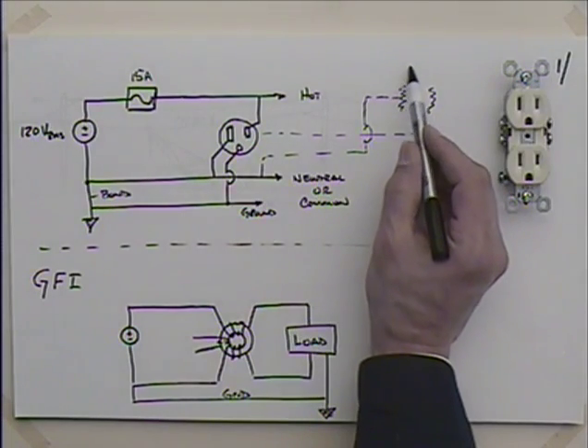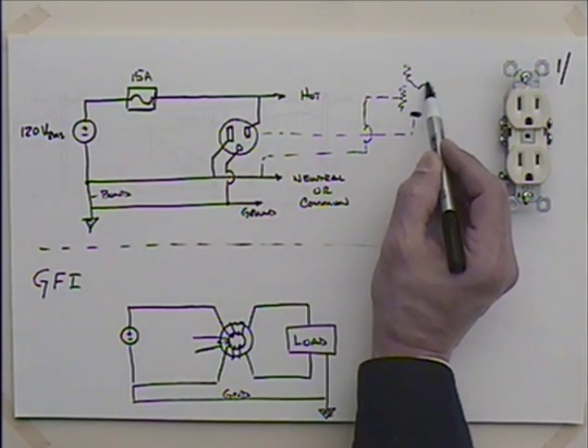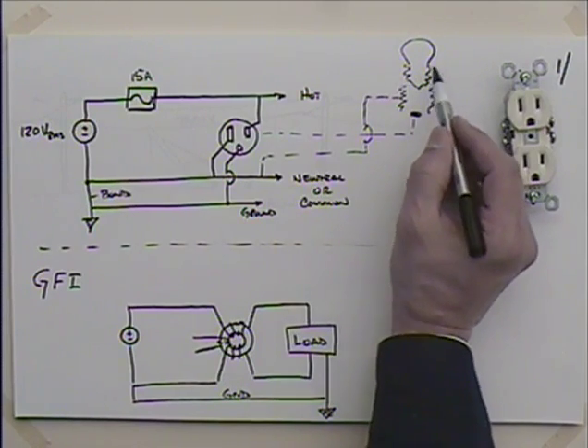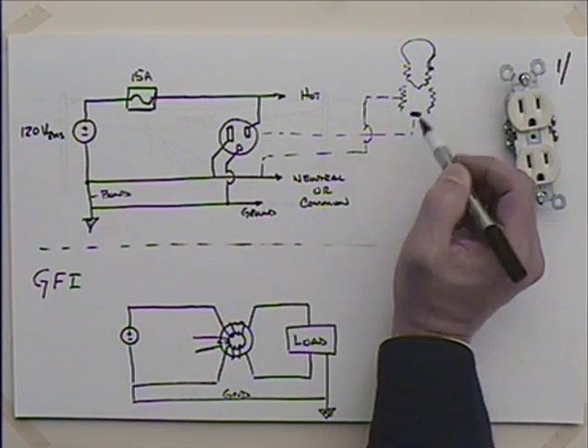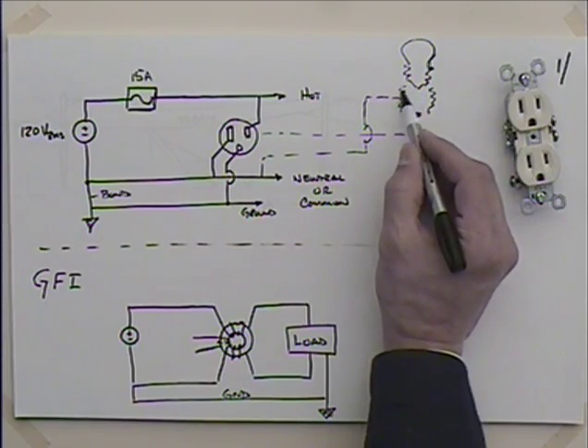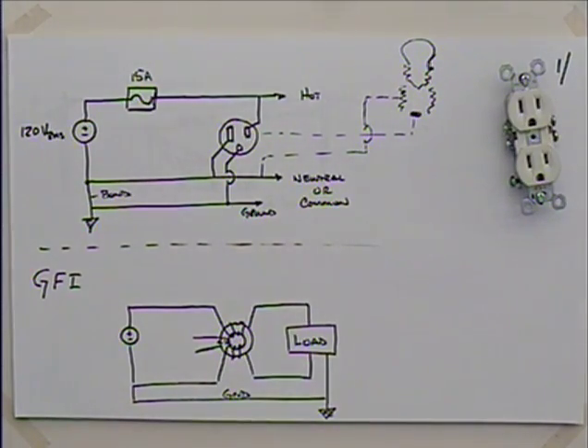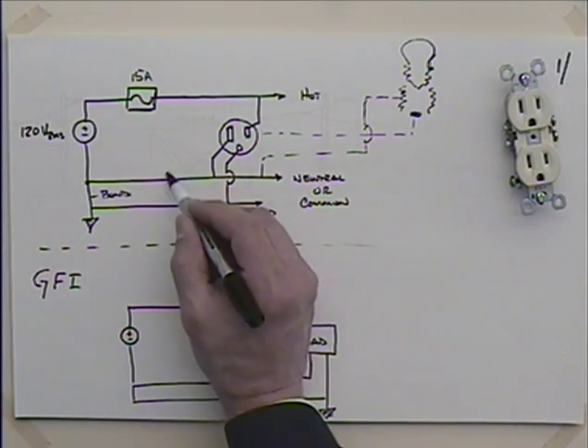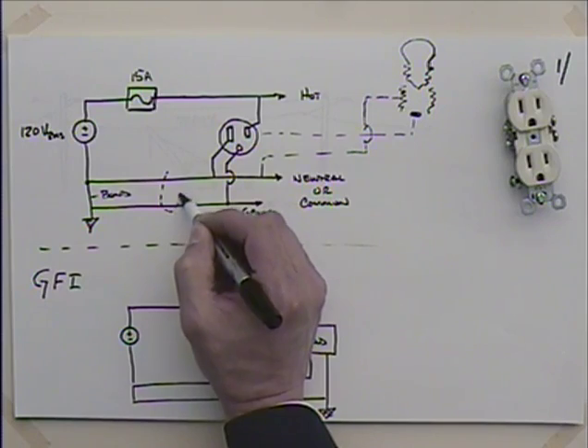The reason is, if you were screwing in the light bulb and you happen to have some sweat on here or it got onto this, would you want this to be the hot side? You would not. You would want this to be the common, because if you look at this neutral or common, it's actually at the same potential as ground.